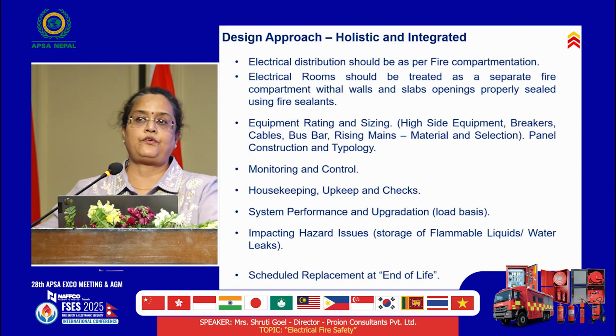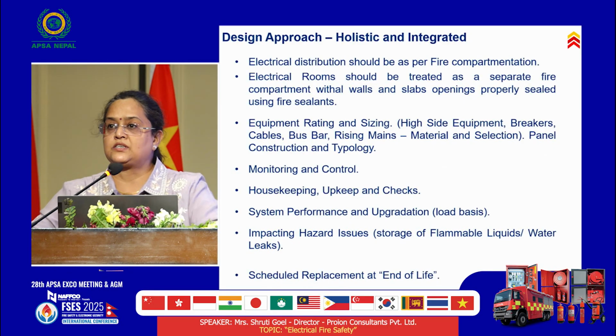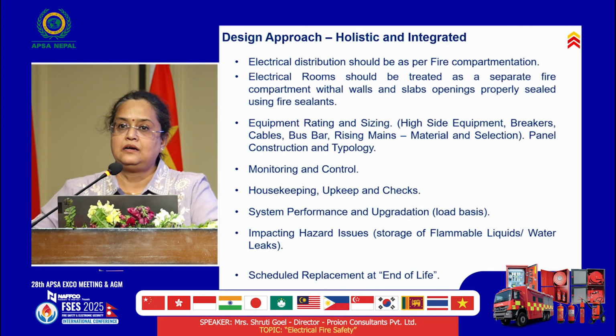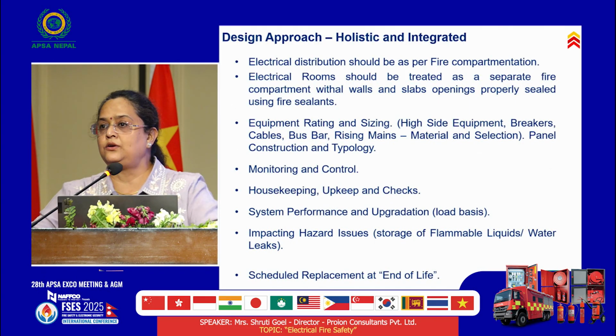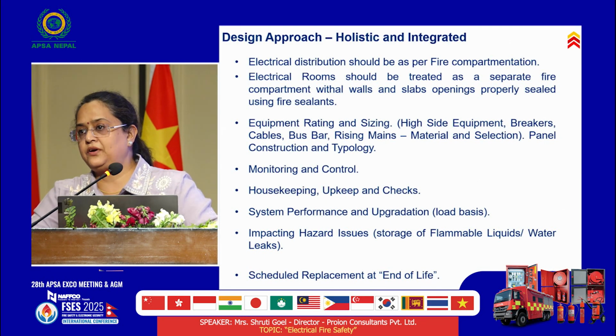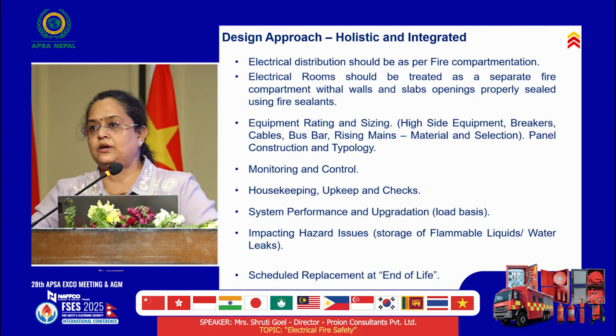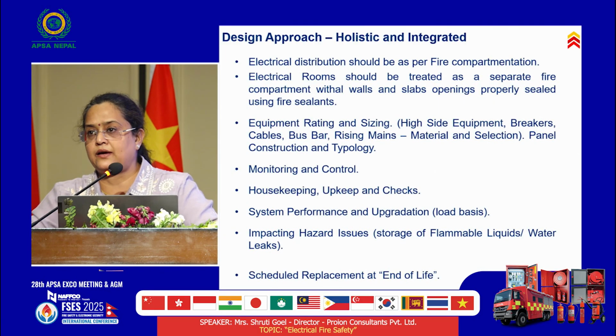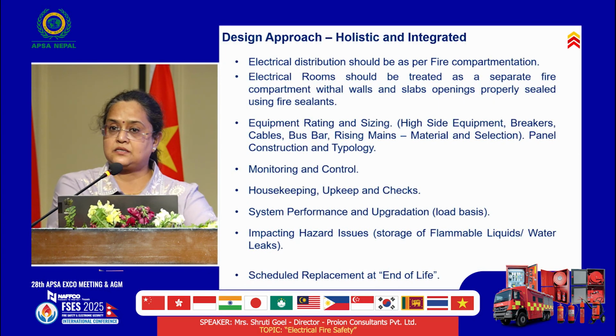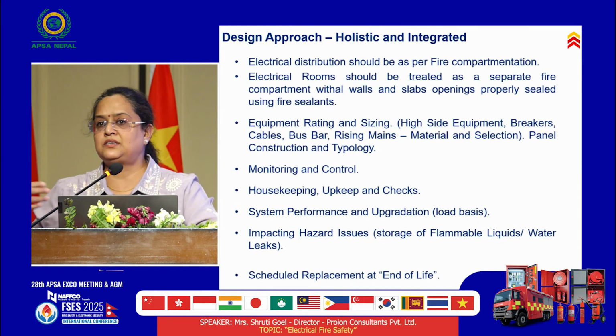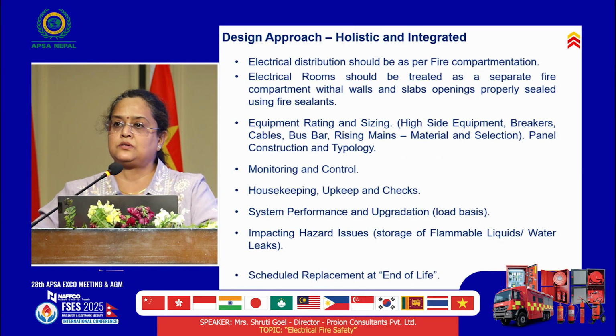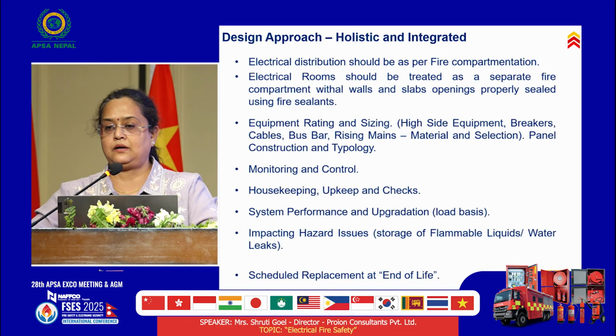There are now fault monitors also, which can tell you what the leakage current is in the earthing system or in the neutral cable. So whenever the level goes up beyond the safe limit, you can always check your design, you can always check your system to see where the leakage is happening. Control it before the fire happens. There are systems which are not to be bypassed, which a lot of times we bypass because of continuity of service at that particular time, which can cause fire.